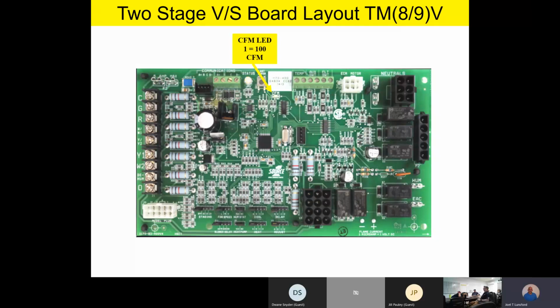But this little light right here is just a quick little visual cue. Anytime the fan is running, that CFM light is going to flash one time for every 100 CFM. So if you're taking a look at it, and let's say it's flashing 10 times, that tells you you're blowing 1,000 CFM. If it flashes 12 times, 1,200 CFM, and so on. So one flash of the LED equals 100 CFM. Any questions or comments so far on what we're looking at on the control board? Everybody good? We're good on this. Okay.